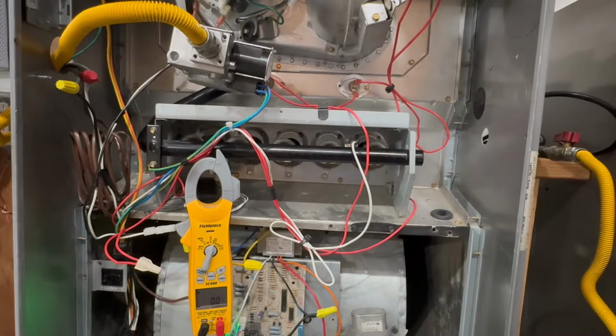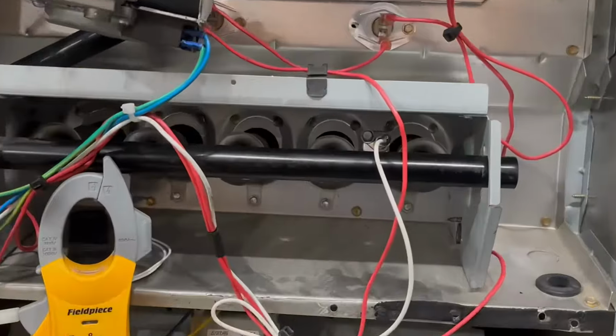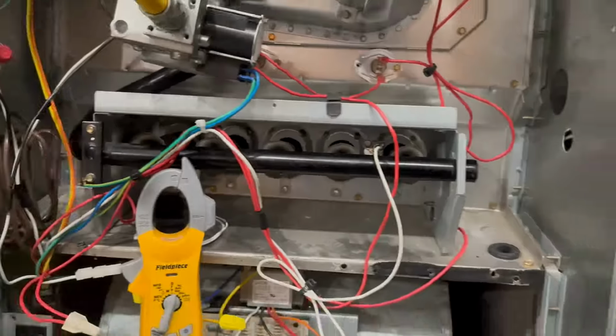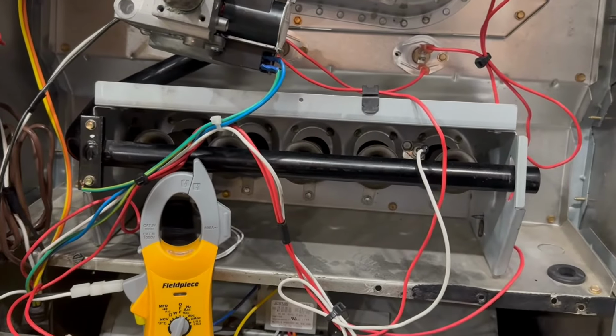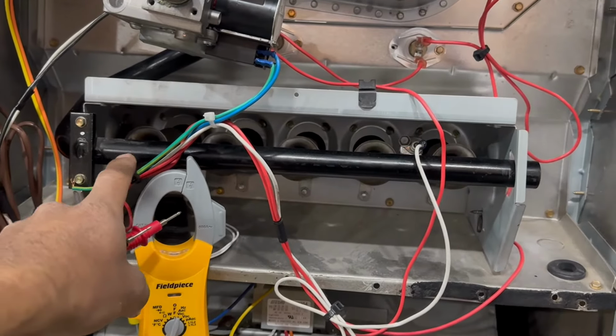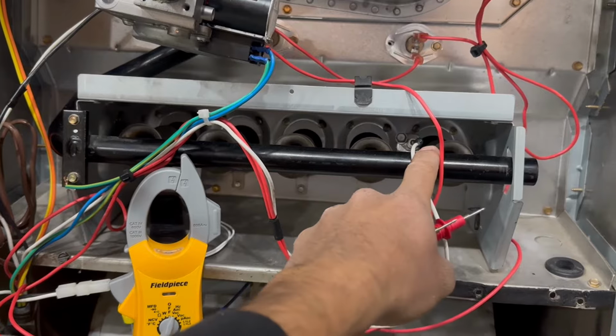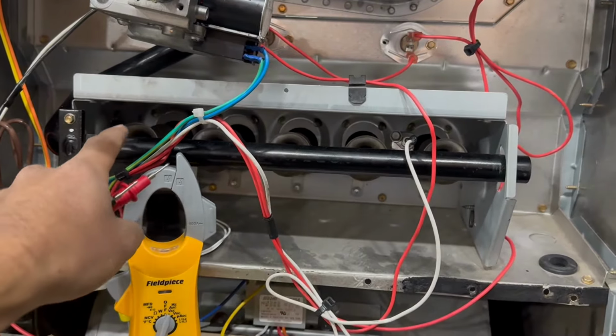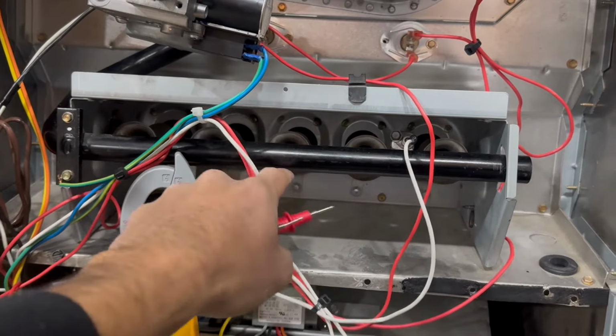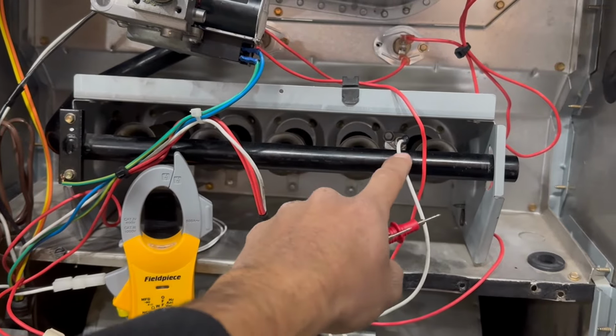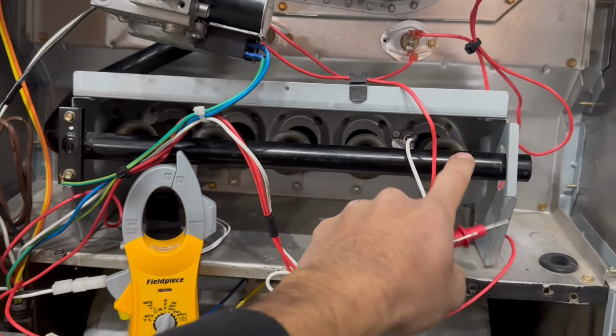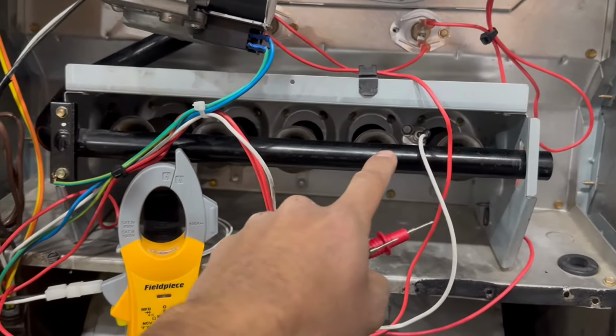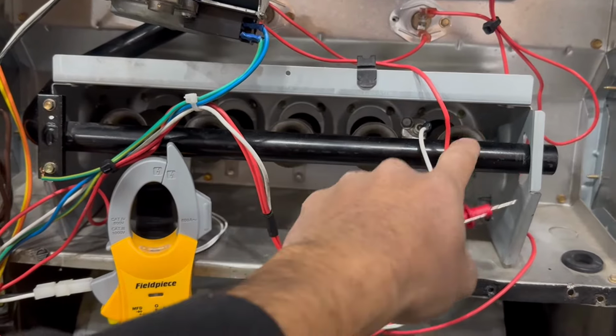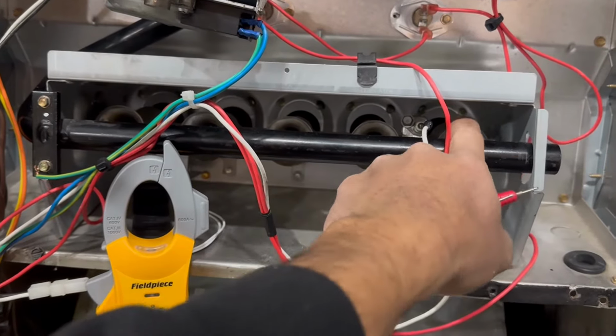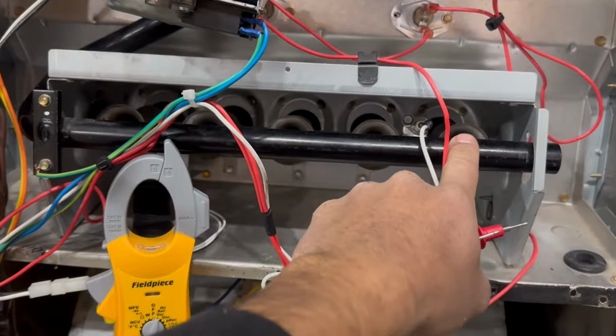F is flame sensor, flame rectification. So in there, this is where you have the flame sensor right there. And it kind of makes sense because your igniter is right here on the first one. Your flame sensor is all the way at the end. So when this ignites, boom, flame, flame, flame, flame. And then they put the flame sensor at the last flame. Because if they were to put this one on the fourth one, well, what if something were to happen right here on this one? It wouldn't be able to detect it.